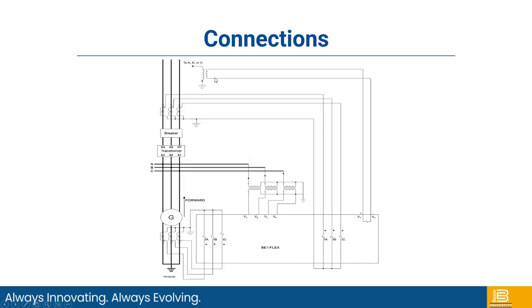Here is the connection. So starting at the top, you have your line to neutral connection for your VX to do your sync check or auto sync. You have your high side CTs for the transformer and also protection for this breaker, which is the high side breaker. Then you have your 3-phase on the generator side. Typically here in between the generator and transformer, you possibly could have a set of CTs there as well. And then also your 3-phase PT input for your voltage measurement and voltage protection for the generator.